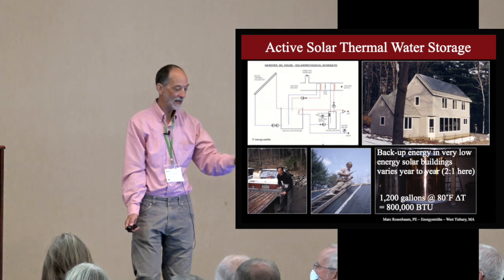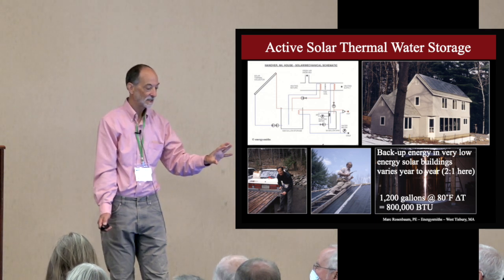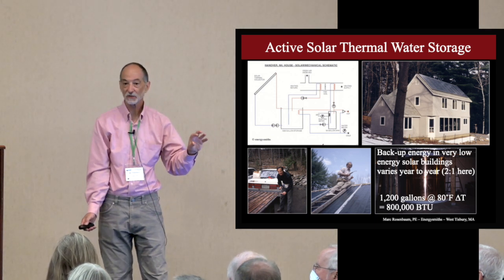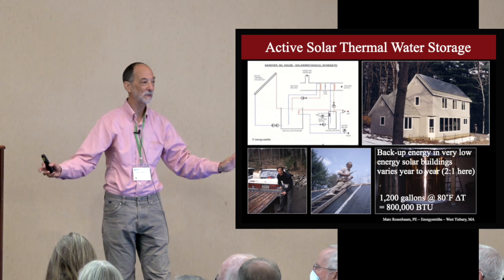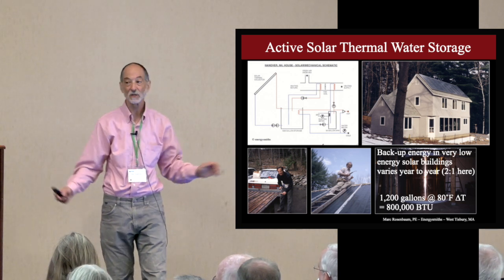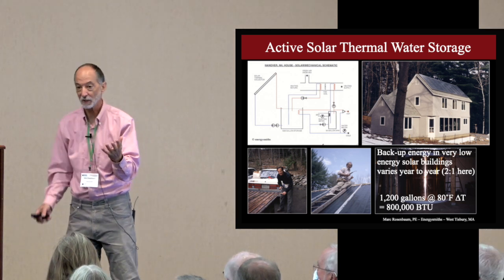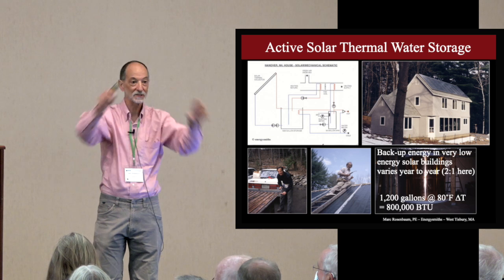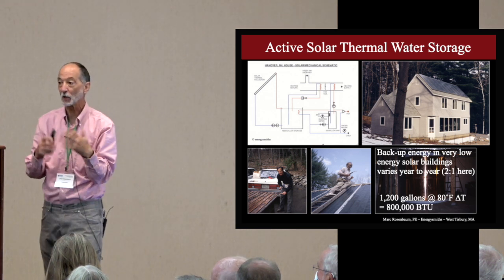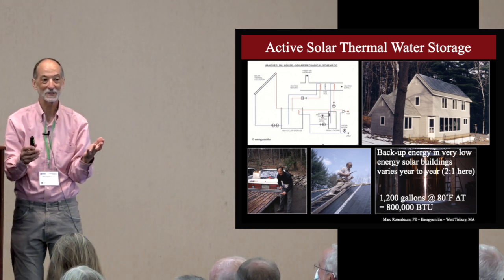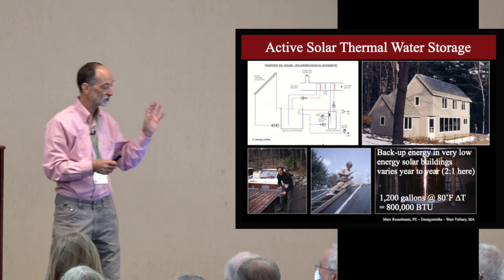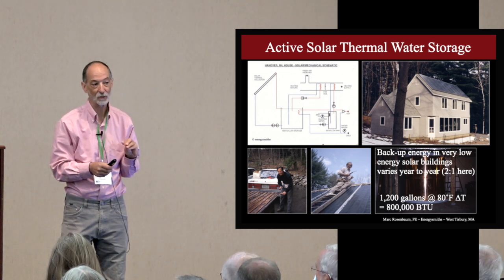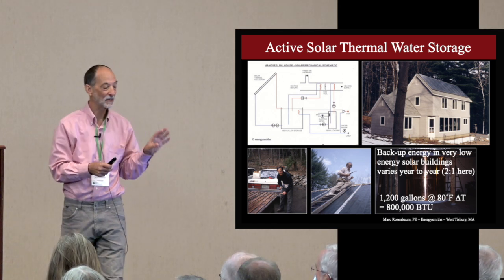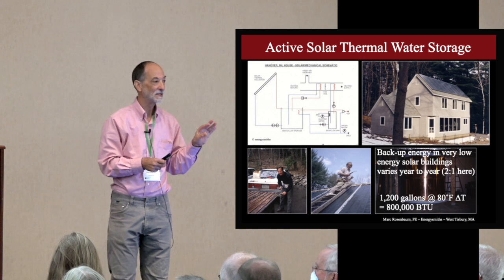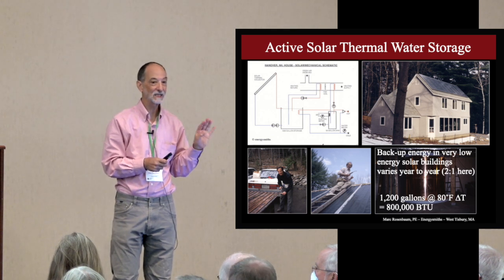Then what you have here is a fan coil—a conventional 4-pipe fan coil with a chilled water coil, which are big, lots of A coils, because chilled water coils work at low temperature differentials compared to heating. So the solar water goes into the chilled water coil, and this house can be heated at 30 below with 95-degree water. That's a key thing here.